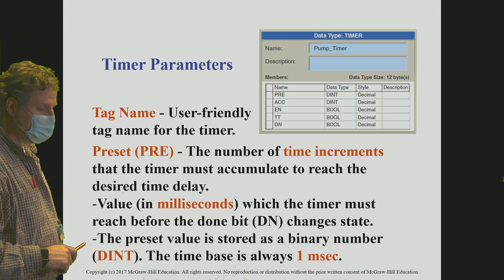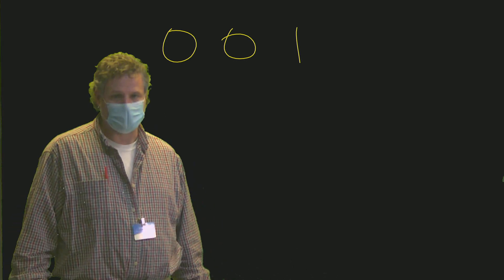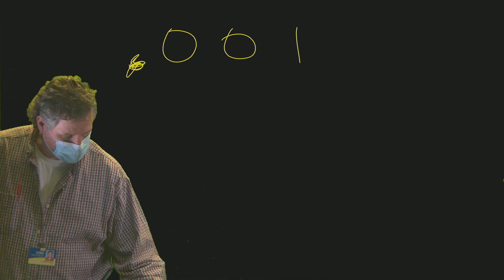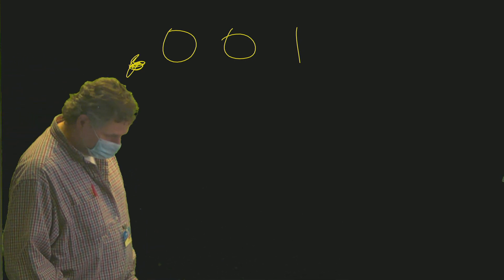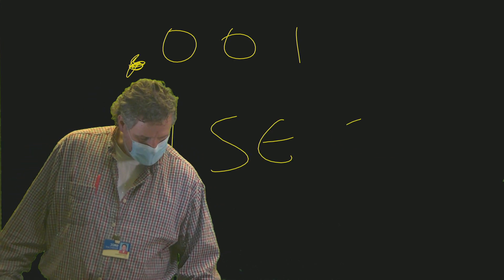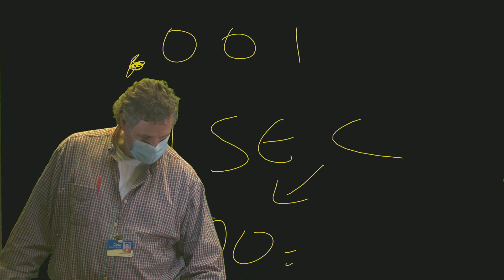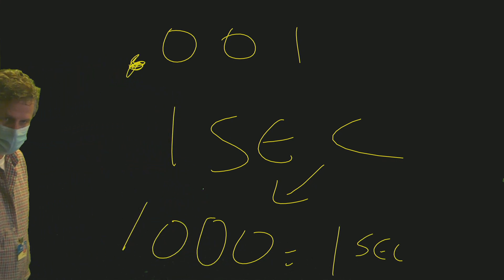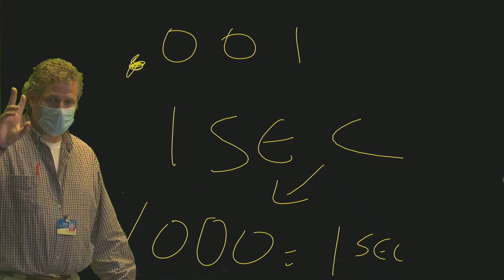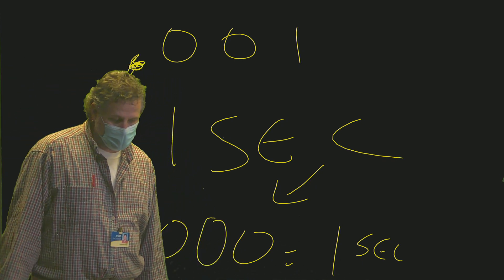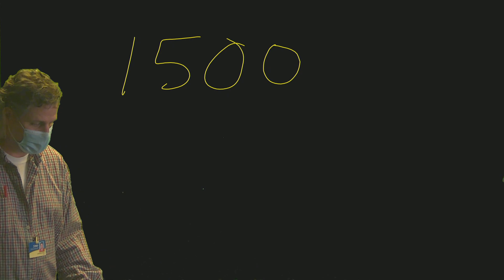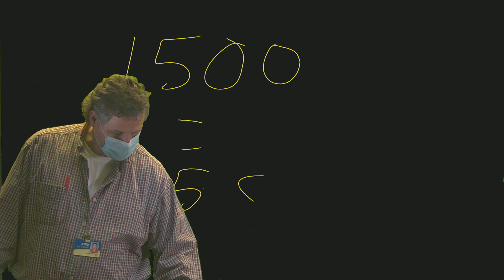The last piece is the time base. The time base is always one millisecond — that's 0.001. So to get one second, what value would you put in? You'd have to put a value of 1,000 to get one second. Keep that in mind — if we're asked for 1.5 seconds, we would enter 1,500, which equals 1.5 seconds.